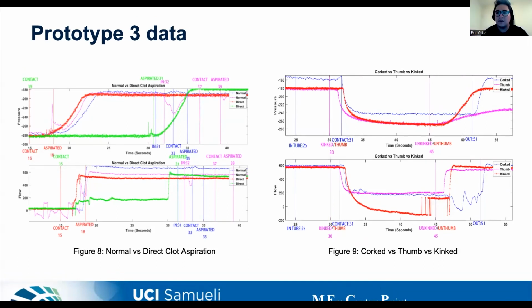On the right, we have an overlay of a cork, a thumb, aspiration, and a kinked catheter. This is meant to differentiate and discern what's going on within any given cork-like system occurrence, such that looking from left to right, we see that water flows through the system. It then comes into contact with a condition: it is either kinked, the thumb is in contact, or it is corked with a clot, and it goes to a sudden value, such that it is almost approaching a vacuum. And then once it is released, we see a sudden change in slope. This area allows us to differentiate between the corked, thumb, and kinked.